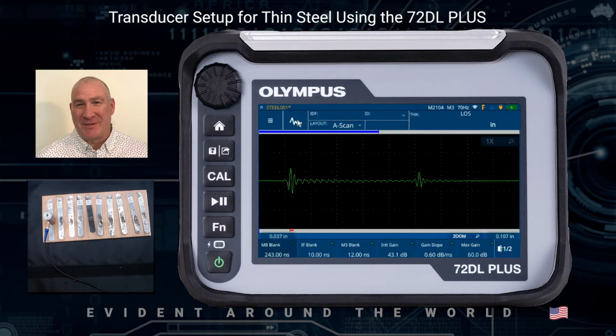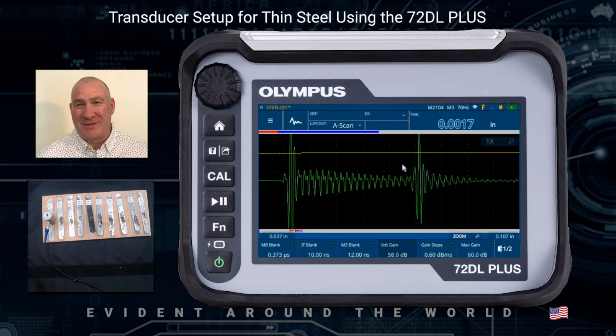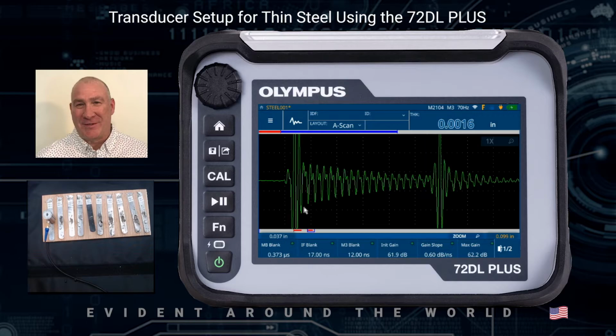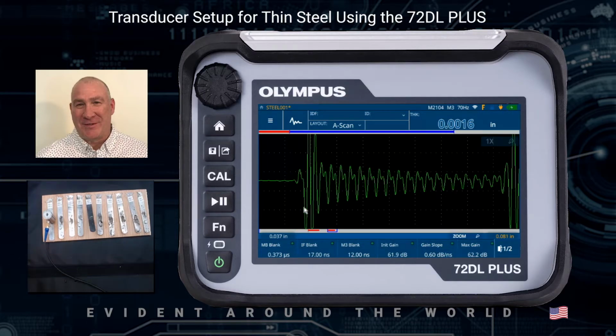Oh, actually I need to adjust my main bang blank first. So now that my echo is within the window, I can go up and adjust my initial gain using the knob. I'm going to turn that up, and we can see we're starting to see our echoes here. Now, the one thing that we do notice is that we are making a measurement starting on the trailing edge of the interface echo. So I want to get away from that a little bit so I can get to these clean multiple echoes. I want to touch on the interface blank and use the knob to kick that out a little bit. So now I'm actually making detection between multiple backwall echoes. Now I can also go back into my range and spread this out a little bit so we can see it a little bit clearer. Okay, so that looks pretty good.